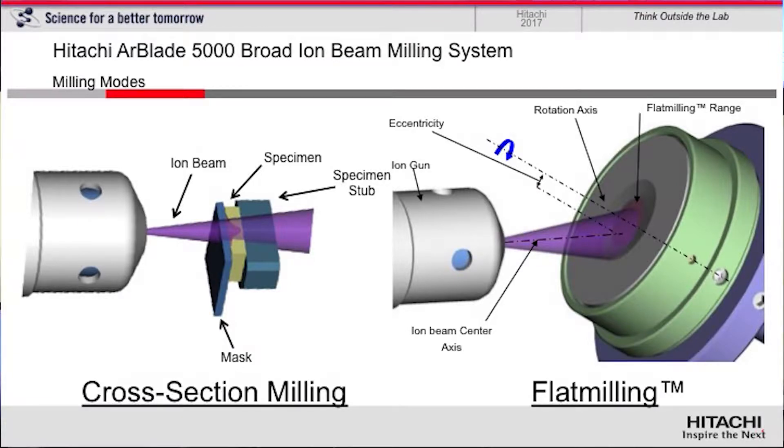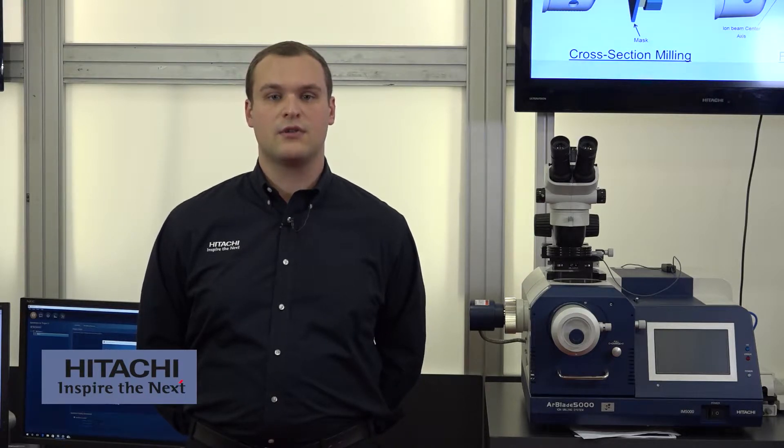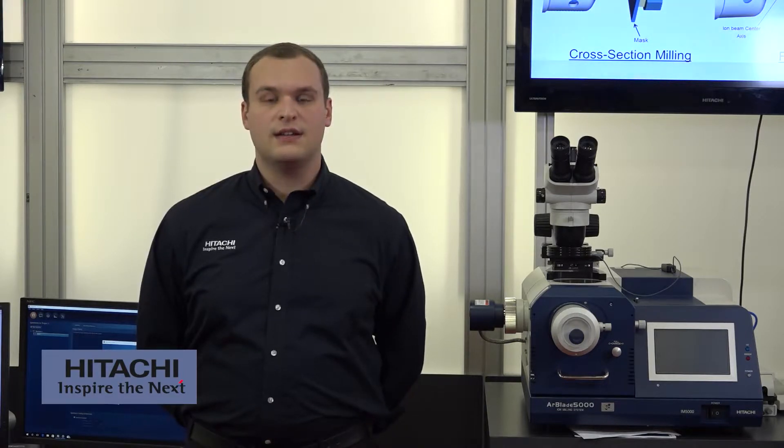The ArBlade 5000 features a dual function stage design for both cross-section milling and flat milling. Cross-section milling enables the generation of pristine surfaces throughout the thickness of a cross-section sample up to eight millimeters in width. This is ideal for observation and analysis of grains, inclusions, or the investigation of adhesion of interfaces in multi-layer structures.